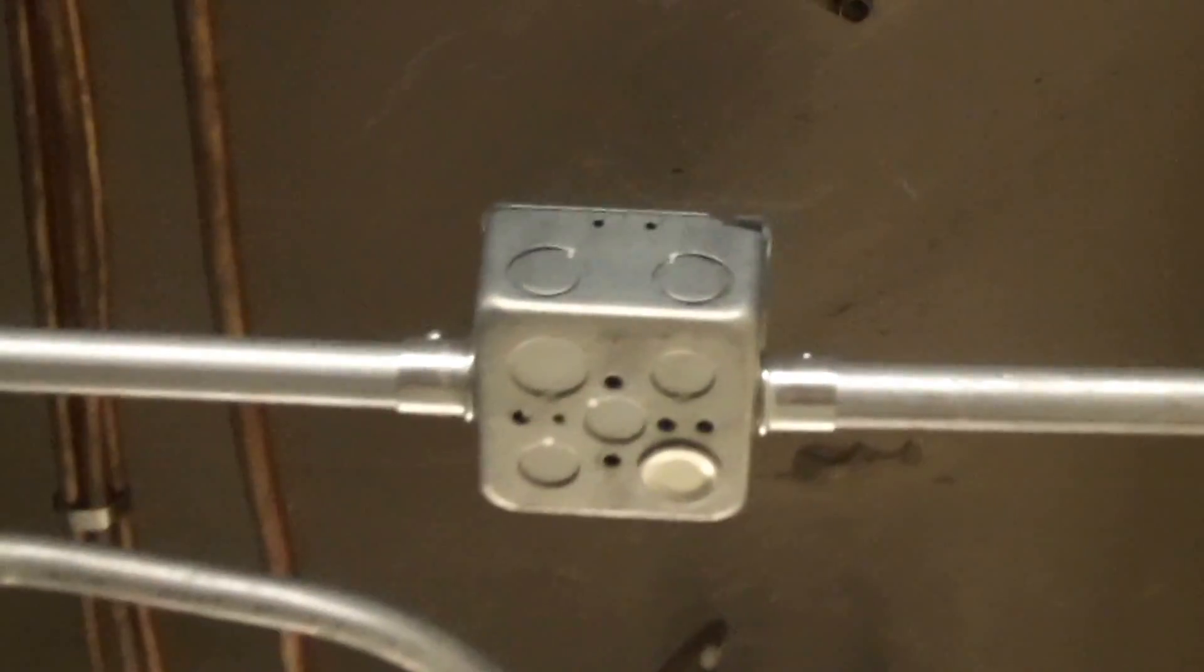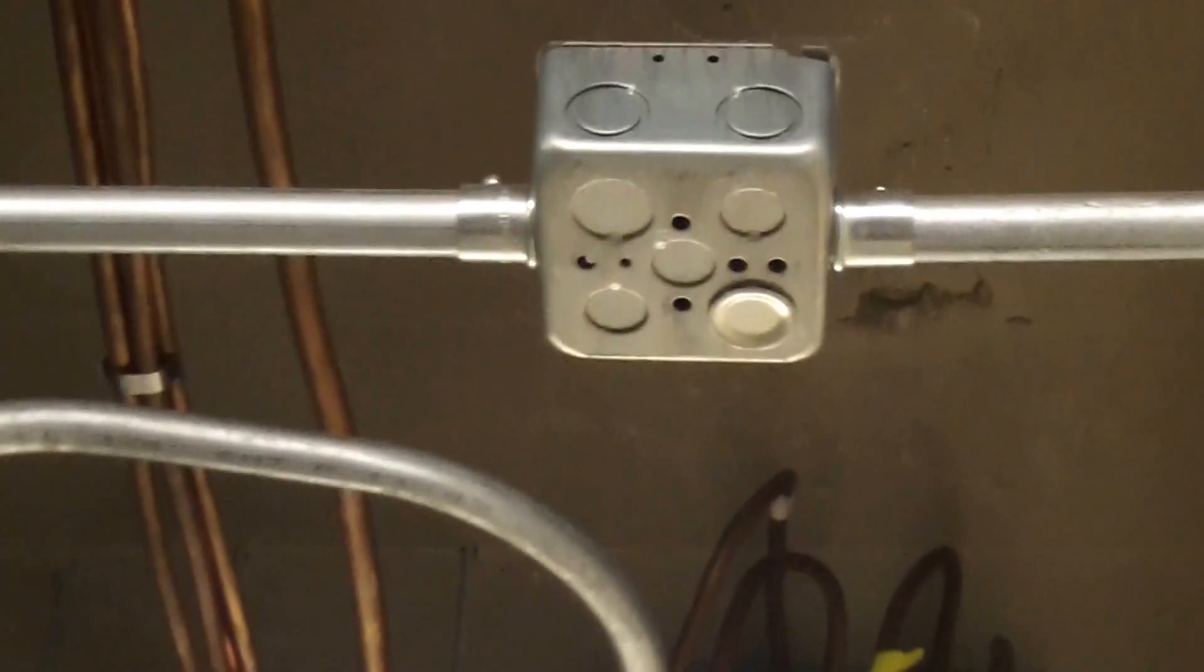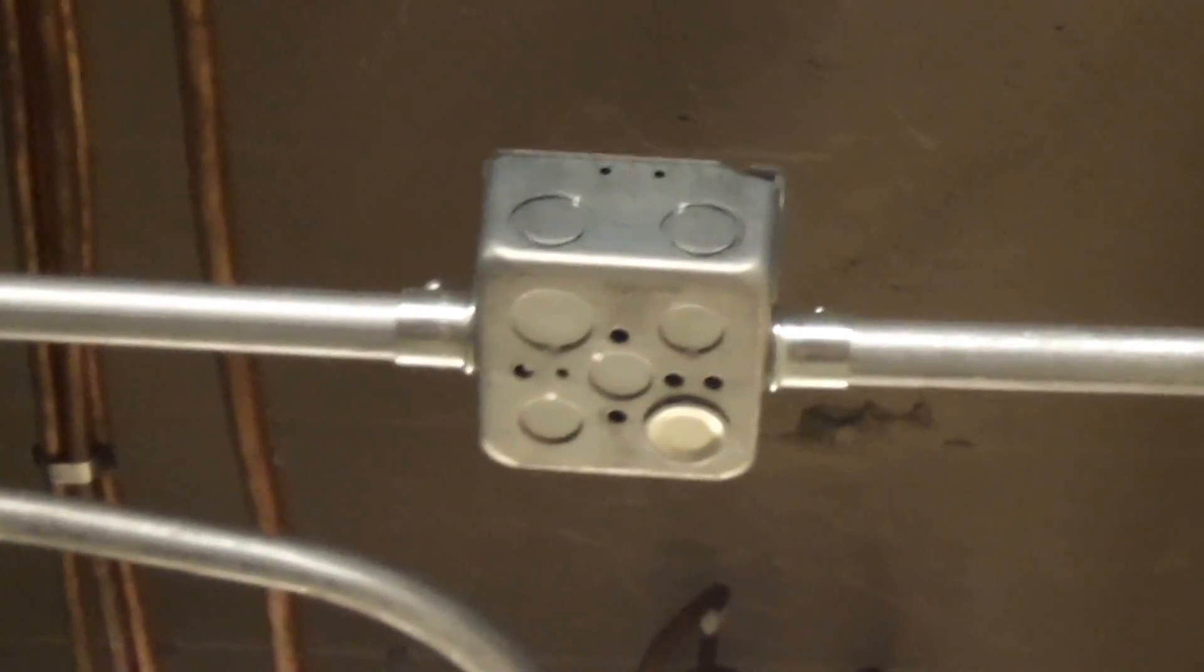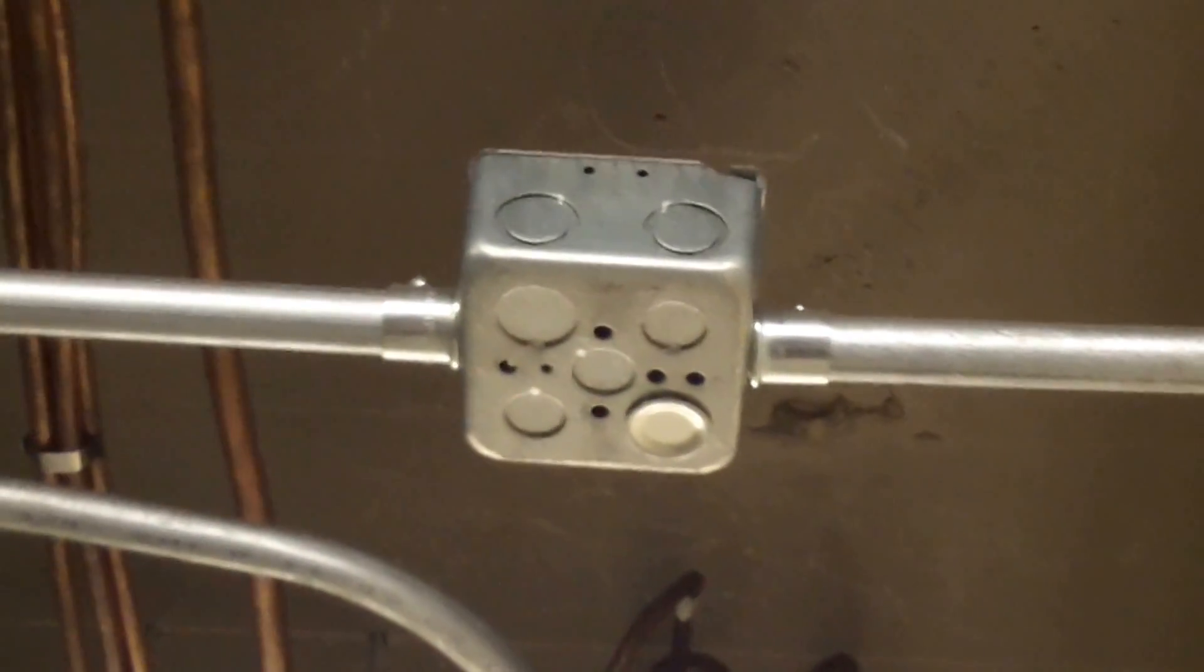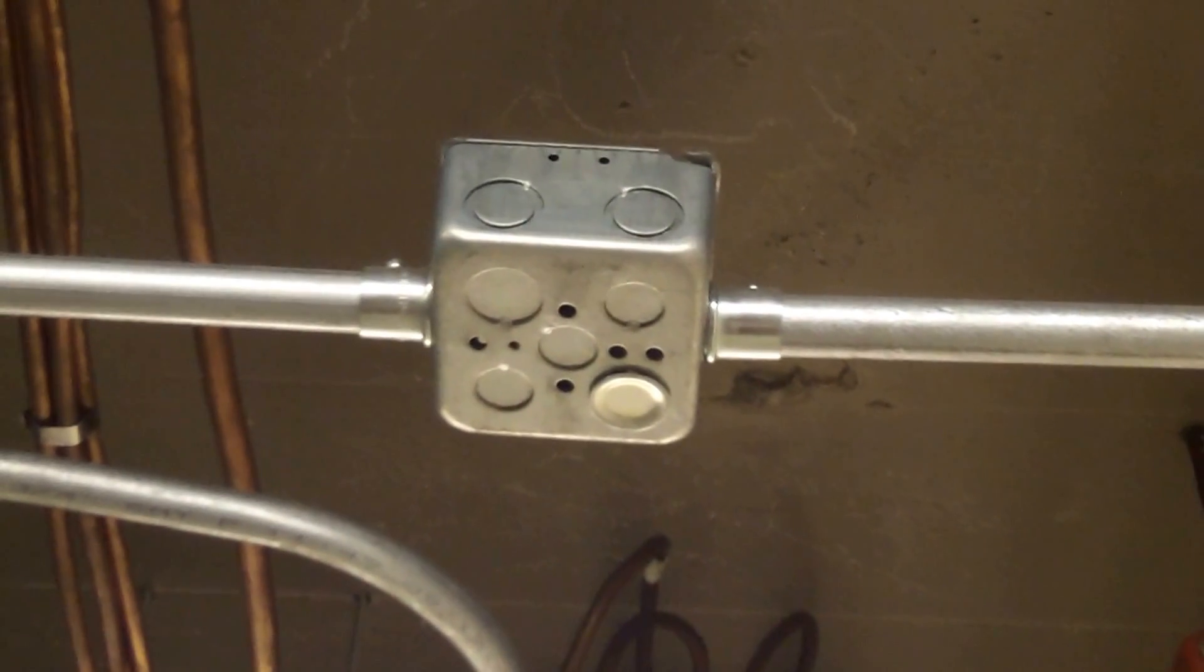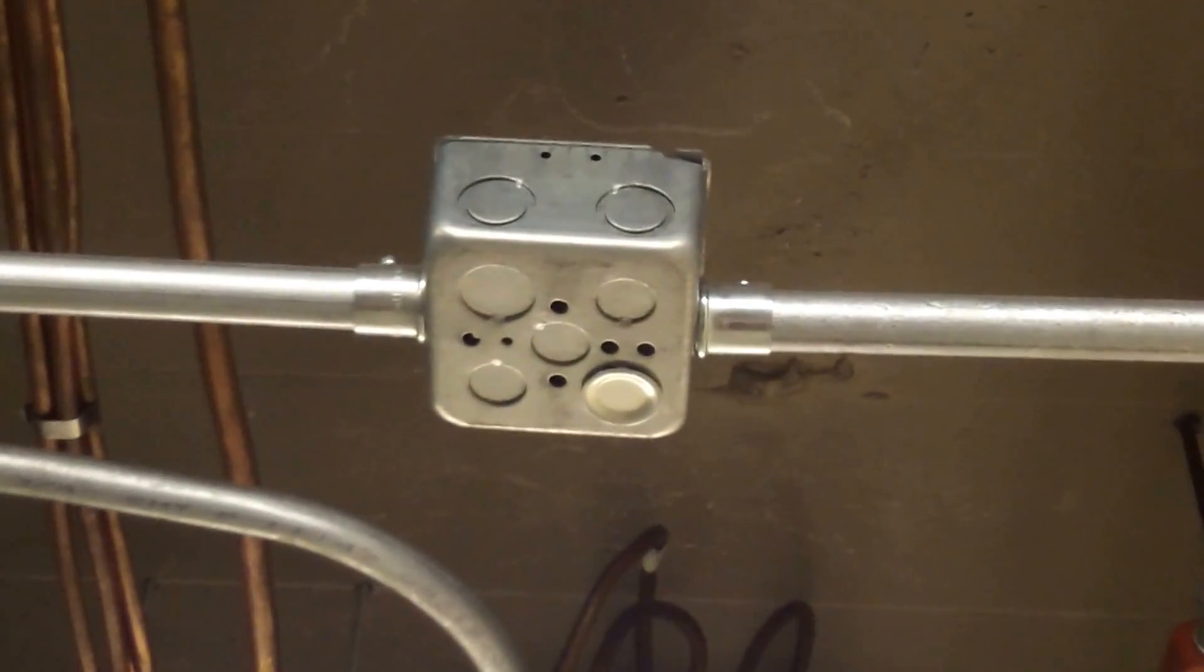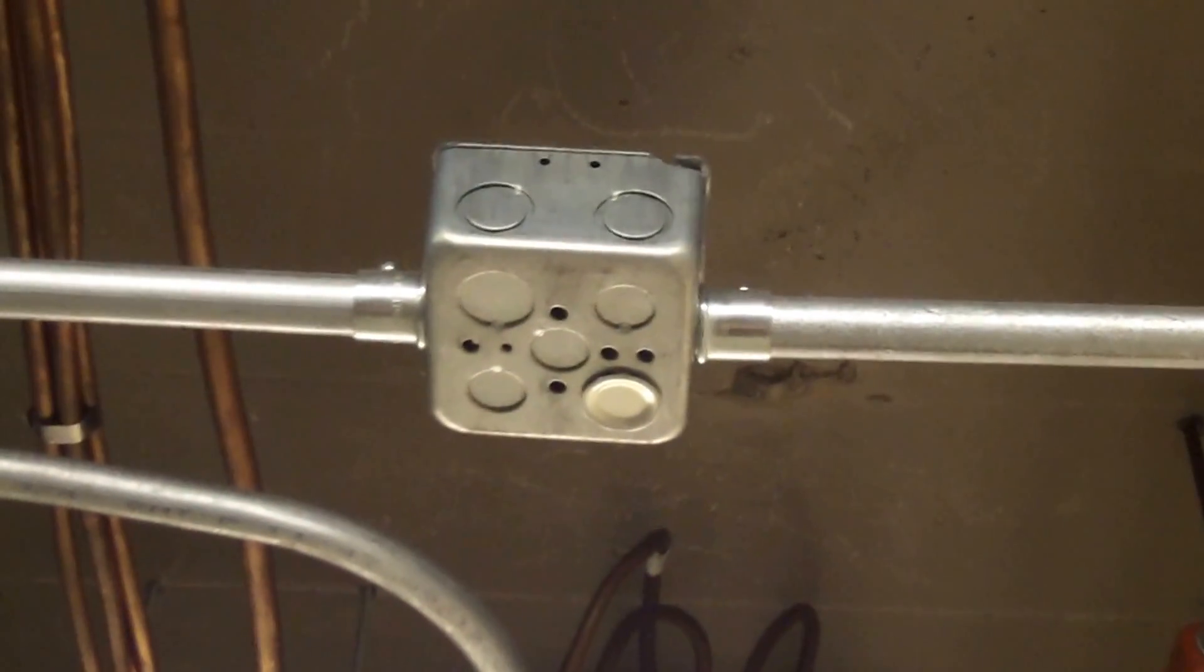We have EMT and EMT connectors supporting this 4-inch square deep box that we see near the ceiling. So again, this is a violation of 314.23e.